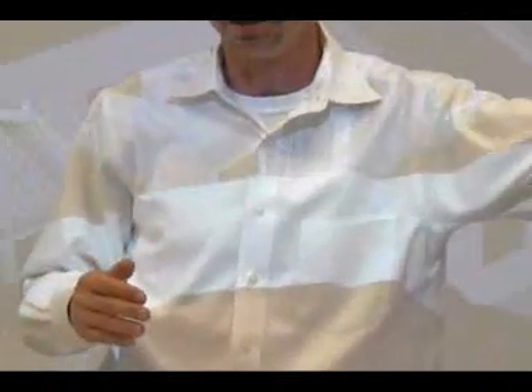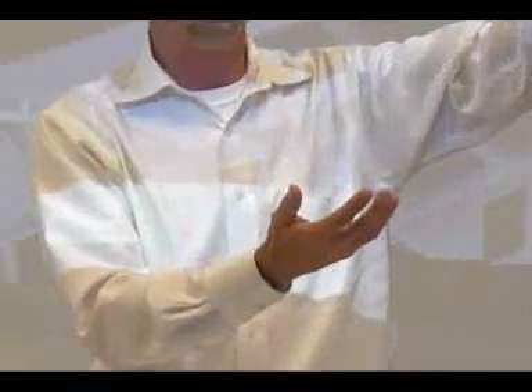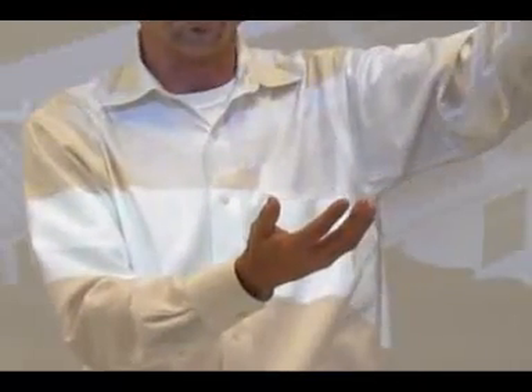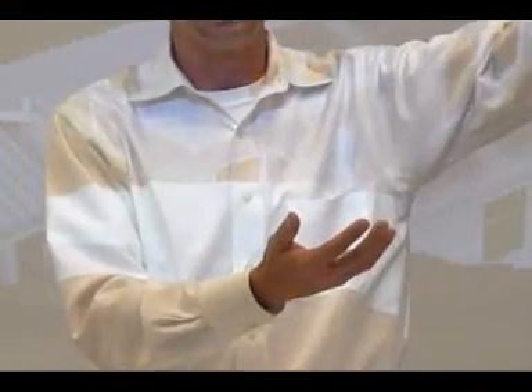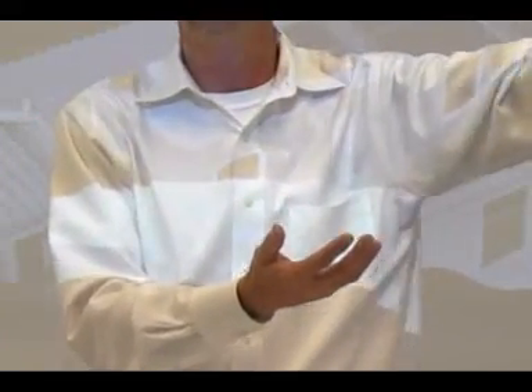The reason being is because as these linemen go out and they're putting those lines back on, they've got it shut off at their substations and their little disconnect areas, and they may think this whole street doesn't have any power on it. But if you're backfeeding 240 volts up through that 5, 10, or 15 kilowatt transformer, it's backfeeding that line 19,000, 22,000 volts. You can kill somebody. That's why it has to be listed by UL.